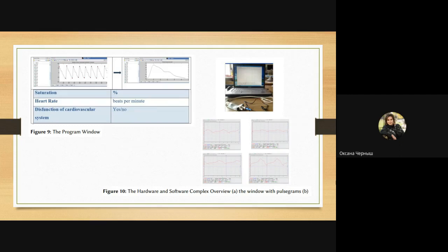The tissues through which both light quantities pass are a non-selective filter and evenly attenuate the radiation of both LEDs. The degree of attenuation depends on the tissue's thickness, skin pigment, and other obstacles in the way of light. Hemoglobin, in contrast to tissues, is a color filter, and the color of this filter is affected by the level of oxygen saturation of hemoglobin.